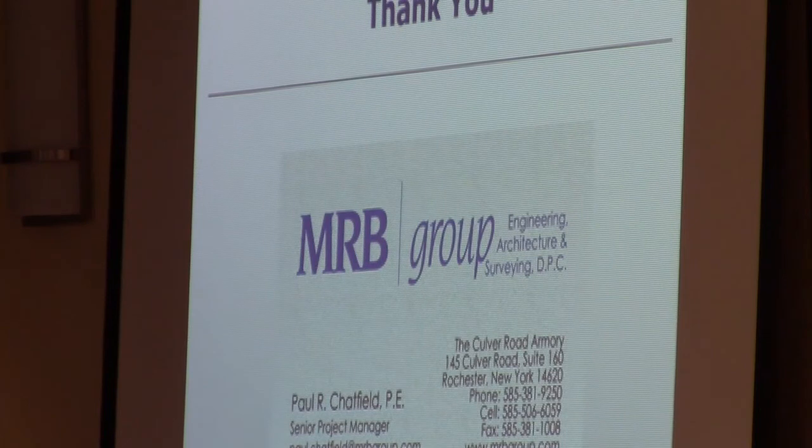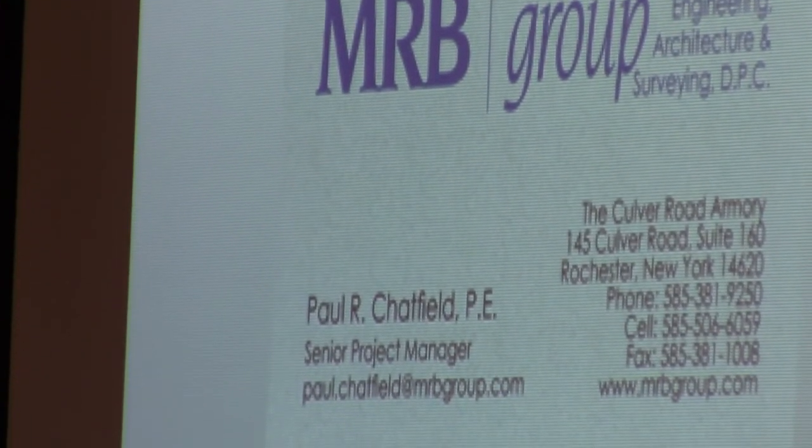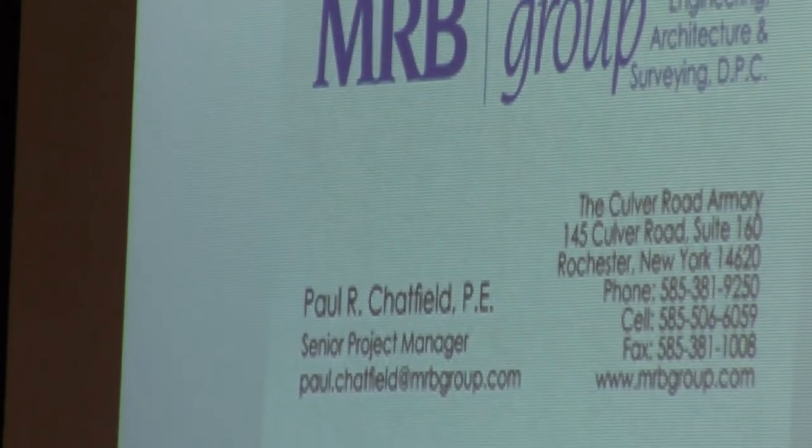Yeah, I actually got a question. So, Paul, once this project is all done, what is the lifespan of that pump station? Well, I think you would be able to get another 40 years out of it. We're going to be making some structural improvements that need to be made to it. And I would fully expect that the pump station itself would. Now, within that 40 years, you're going to have to be replacing some pumps and some motors and things of that nature. But the structure itself and the system itself, 40 years. But certainly short-lived assets, things that need to be replaced periodically.